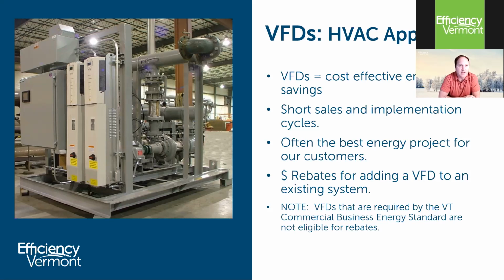Potentially, yes. I need to know the application. As I said earlier, the VFD will do a much better job than the soft starter in handling inrush. Inrush is a very short duration event, but it's an important event, especially if you're a utility company. Across the line starts can cause brownouts or worse. The question in terms of whether we extend an incentive has to do with whether or not the load can be modulated. I didn't hear in that question what the 125 horse was tied to. If it's a pump or fan that can be slowed down by way of a signal, pressure or flow typically, then potentially, yes, we can extend an incentive. If the drive is simply for soft starting, we cannot.